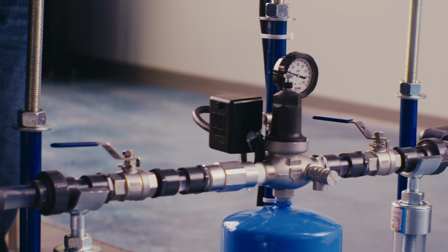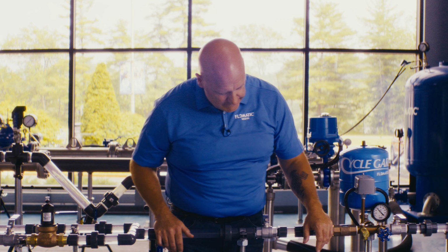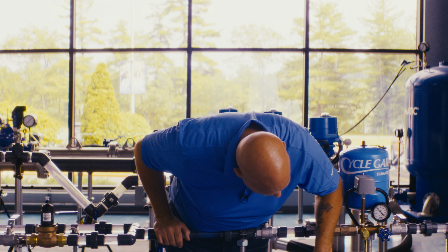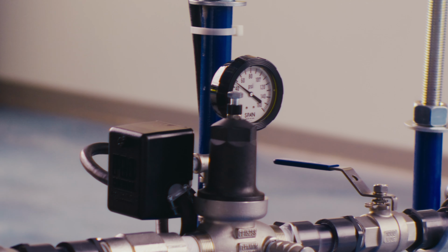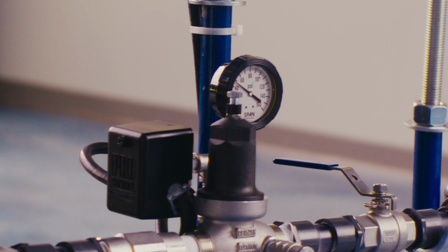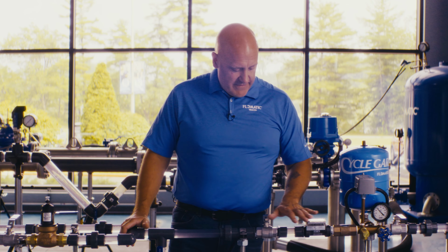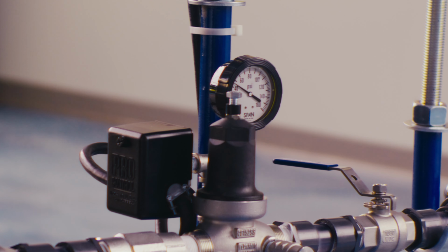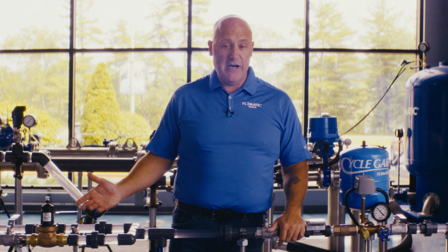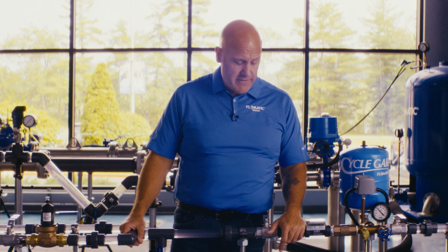Now this Cycle Gard is set up exactly the same as the bronze one, set at 50 PSI. Pump is on, pump is running, and this is gonna run nonstop until there's no more demand on the system. It's gonna hold right up. Pressure dropped a little bit, but our pump is still running. Again, going to keep a nice even amp draw on your pump, keep things nice and consistent downstream. The only time there may be an issue is if our usage exceeds the output of our pump. Other than that, these valves are very robust.